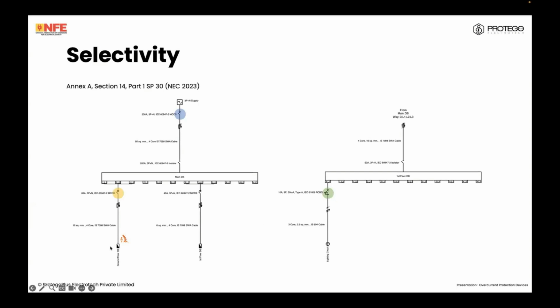a lighting circuit. If we have, say, situation one, a fault on the distribution circuit here, we do not want other distribution circuits to lose power. We do not want this breaker to trip. We only want this one to trip. This is called selectivity. Case number two, we have a fault on this lighting circuit. There are other circuits here. We do not want these to lose power. We do not want this breaker to trip. We only want this breaker to trip. This is what you call selectivity. Only the breaker closest to the fault, or only the OCPD closest to the fault, disconnects. Could be a fuse also.